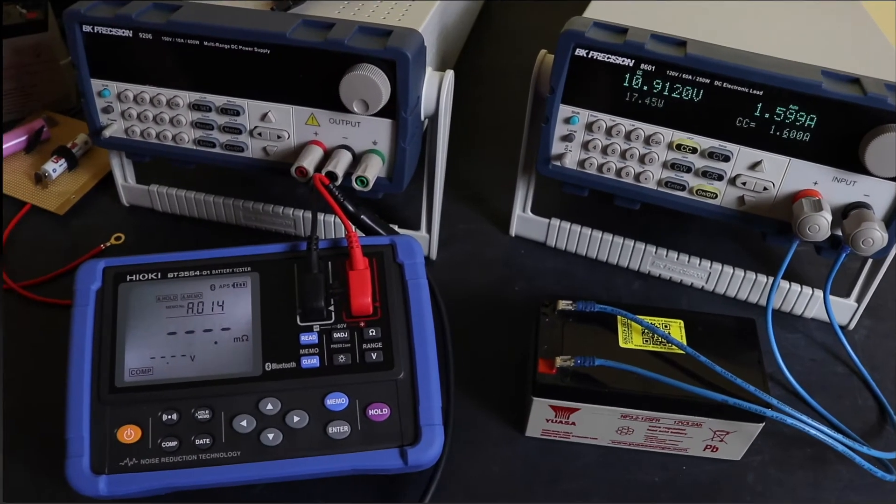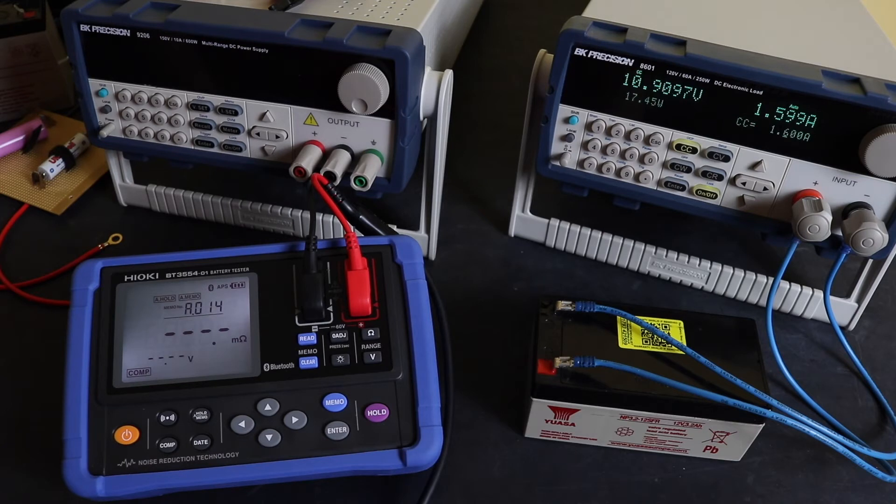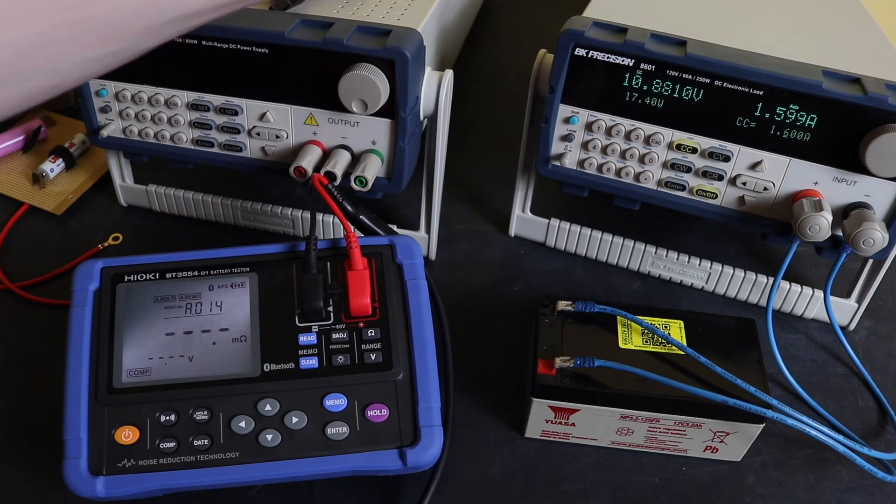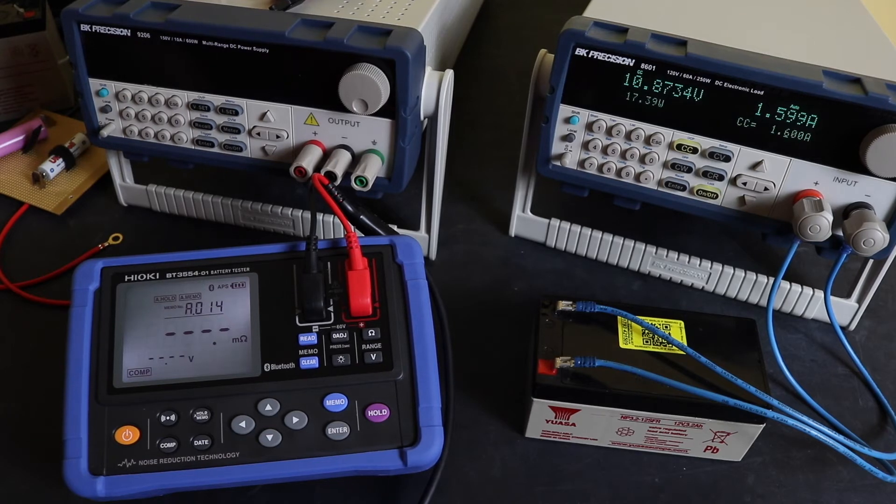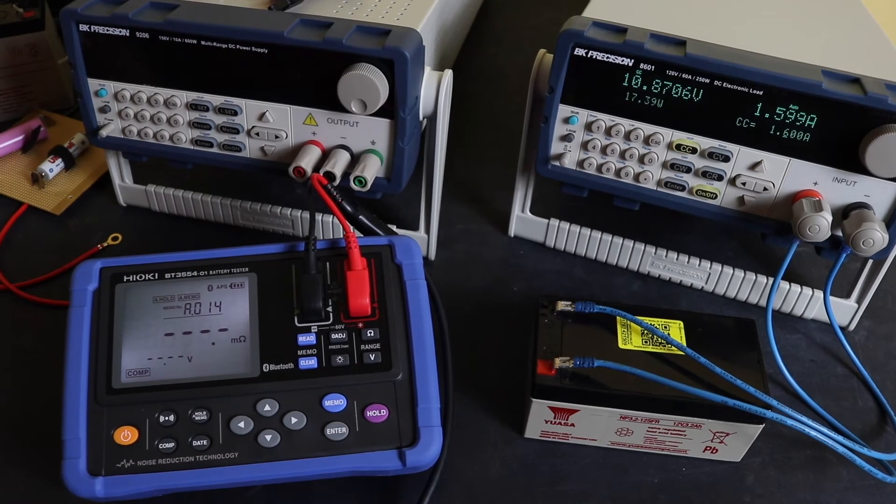Okay, we'll be coming up to the end of the test shortly. This will be the last reading that I make. I'm pretty sure that should stop at 10.8 volts, and with 10.88 now it's dropping fairly rapidly on the right hand side on the voltage meter on the load there. So when it gets about 10.80, 10.75, 10.80, I'll take the final reading.